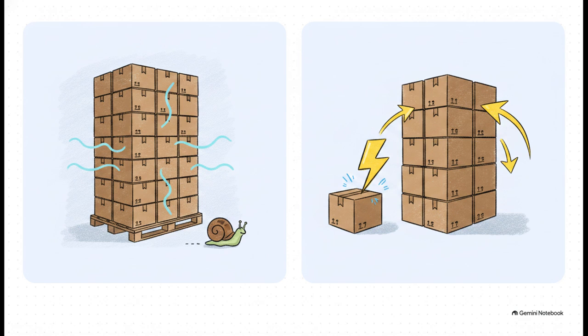Then on the other side, you have E-beam radiation. E-beam is basically a high-powered electron accelerator. It is incredibly fast, knocking out sterilization in minutes, and you can literally just flip it on and off with a switch. But here's the catch. It has very shallow penetration. You absolutely cannot put a massive, dense pallet in an E-beam machine. You've got to break everything down into tiny boxes, about the size of a copy paper box. So for a ton of heavy medical devices, E-beam just doesn't cut it.